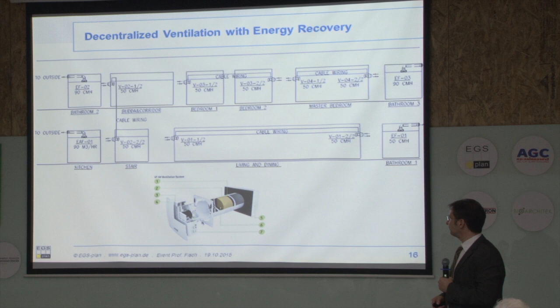But here we have a special heat recovery, it's the yellow part that you see here, and this acts as a regenerative heat recovery, and this is how it works. What you see here is one room in the building. This is the outside, and one ventilator supplies fresh air from outside into the building. It is cooled down in the heat recovery. The heat recovery itself consists of a ceramic material which acts as a thermal storage, and therefore it cools down the air.